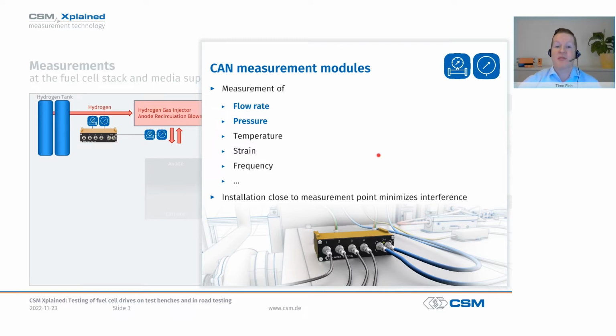What has proven itself for more than 20 years is our concept to collect all measurement data from analog sensors as close to the sensor as possible, digitize it directly on site, and then transmit it by a secure bus system. Because with such short analog sensor lines, we naturally limit external interference to a minimum, and in this way have high quality measurement data available.